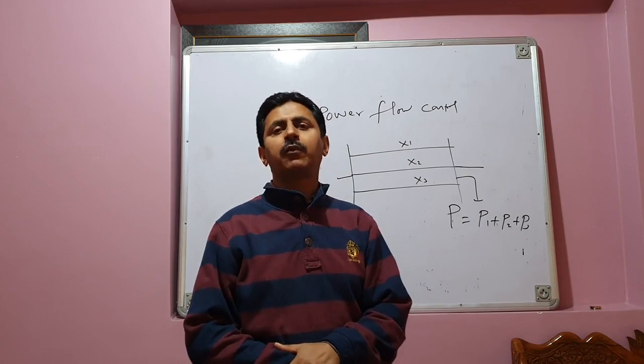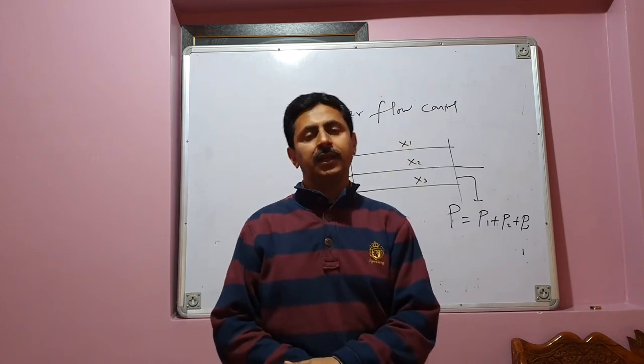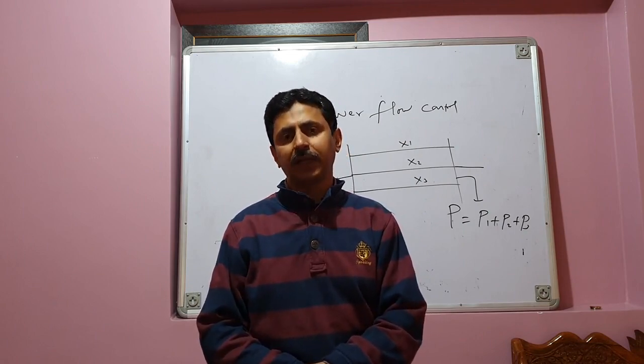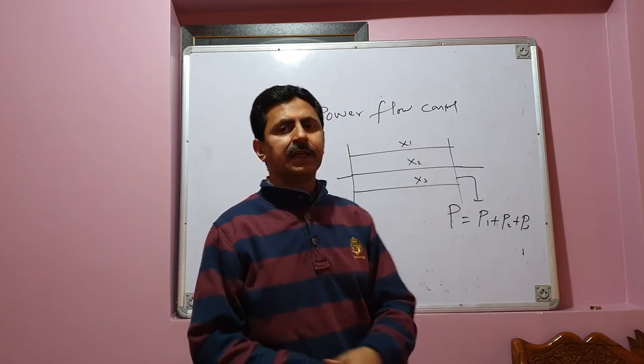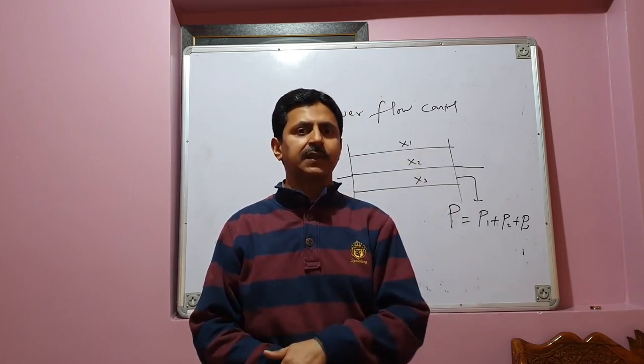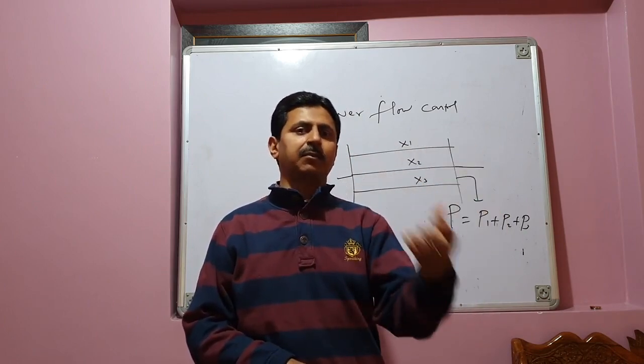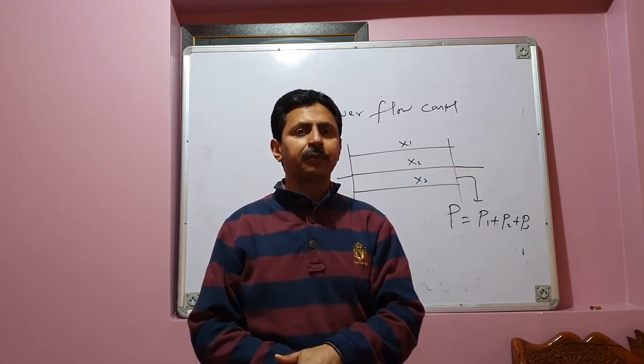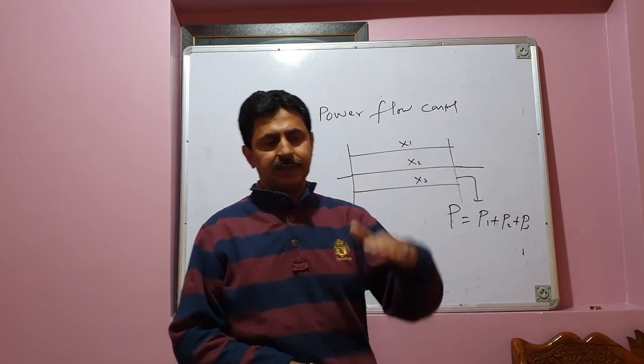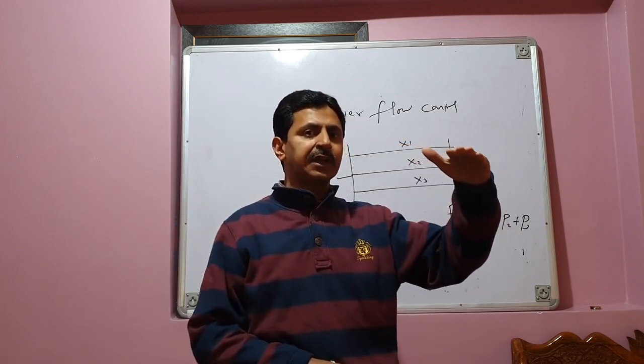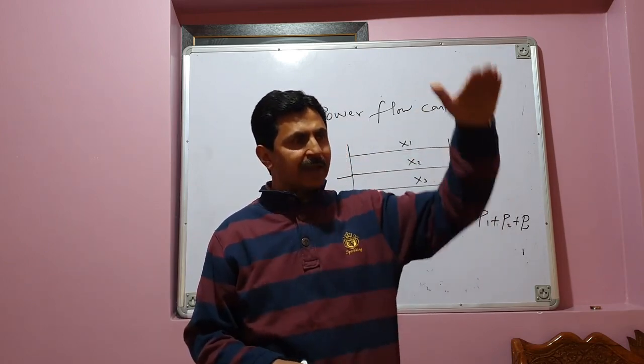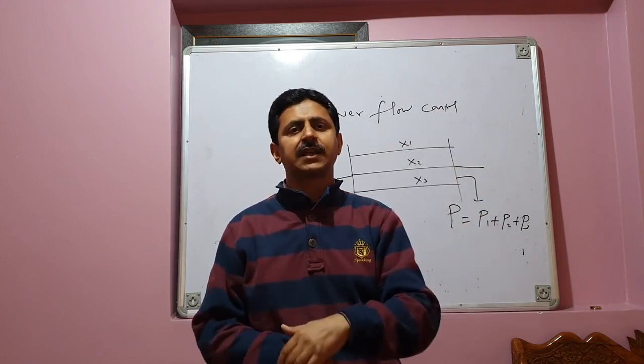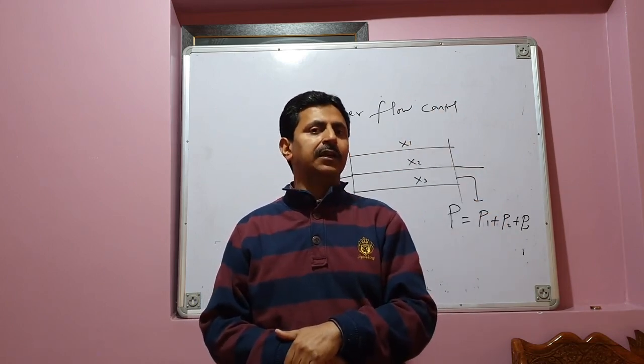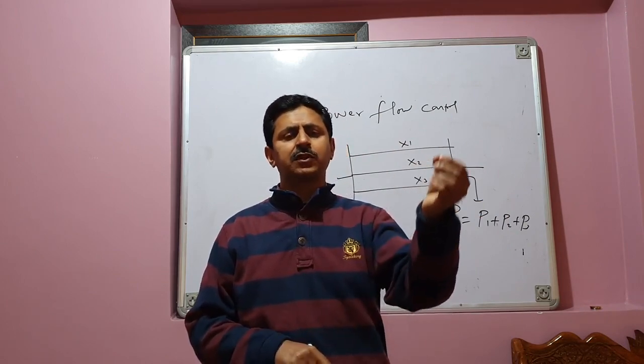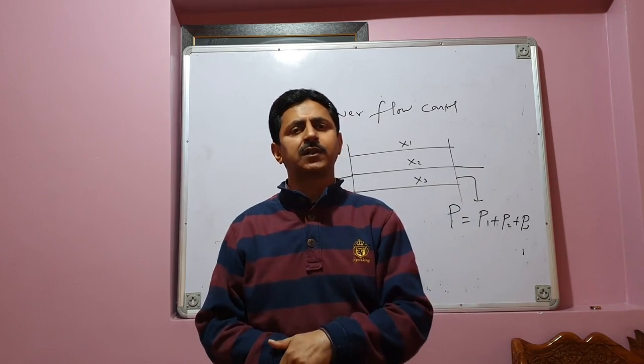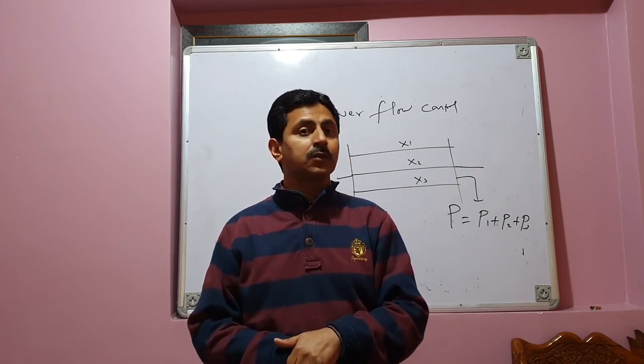The power which is flowing over a particular transmission line is inversely proportional to the impedance of the line. So in this case, the line which has higher reactance or higher impedance will be the line carrying less power. Therefore it can remain underutilized. Say, for example, it has a capacity of transmitting 100 megawatts, but because it is in parallel with other transmission lines and its impedance is high, it may not transmit exactly 100 megawatts of power. It will transmit a small amount of power, say 20 or 30 megawatts, because of high impedance. So it remains underutilized.